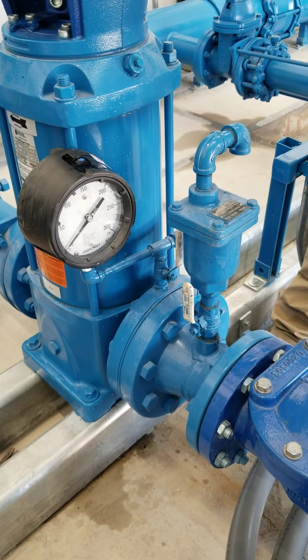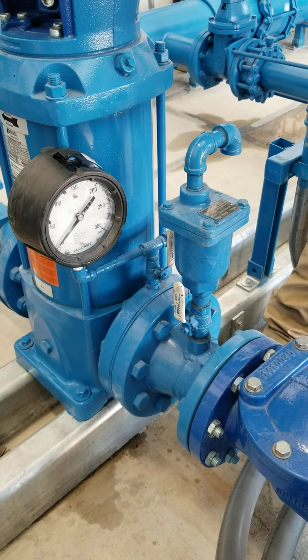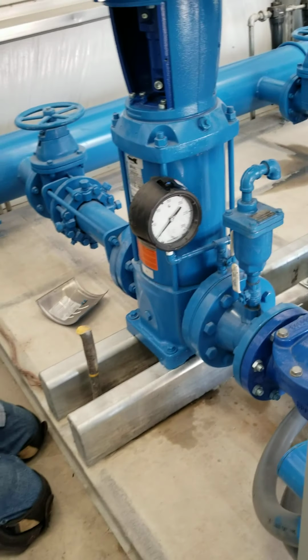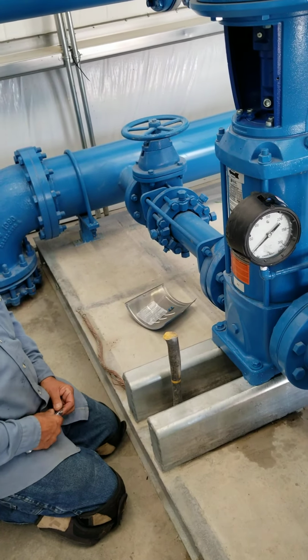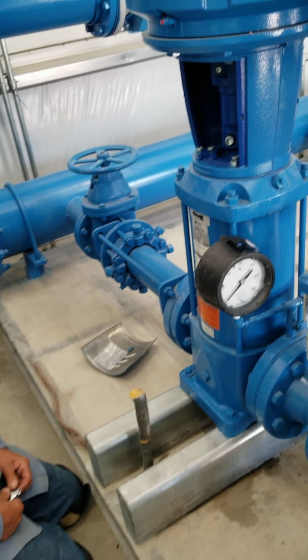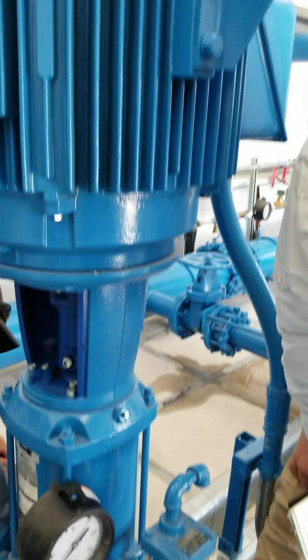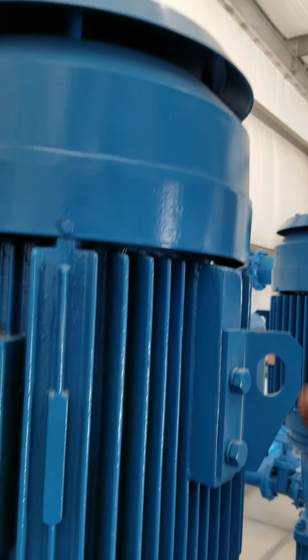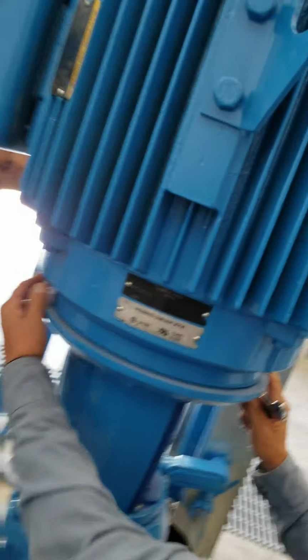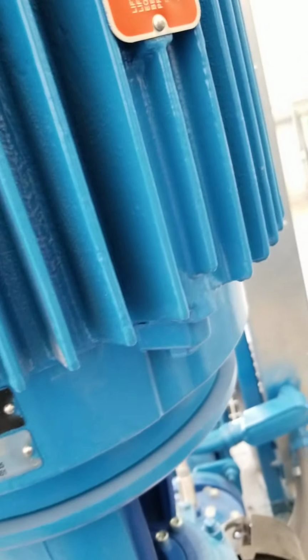How often do the grease zerks on these motors need to be greased? Depending on how much you use them, but twice a year max. Two squirts. It's not a hell of a lot. That's what I was looking for. So on this one, when you grease this side, pull this plug so you don't over grease it. But I couldn't find the one on the top. You may have to take that off to get the one on the top. It's not this one? No, that's the grease zerk, but there's not one on the other side. Yeah, I don't see one. I wouldn't overdo it.